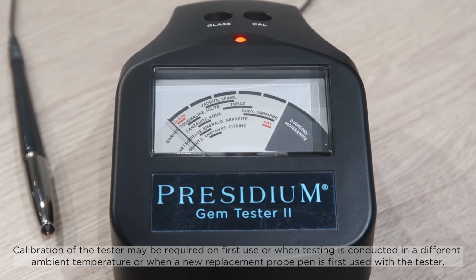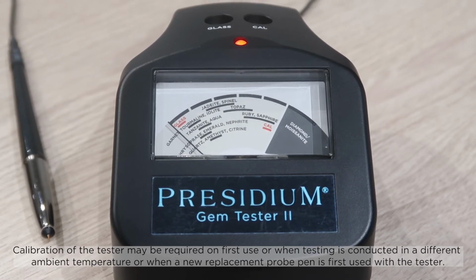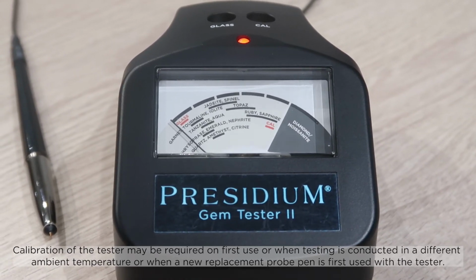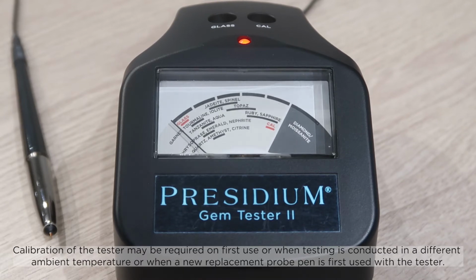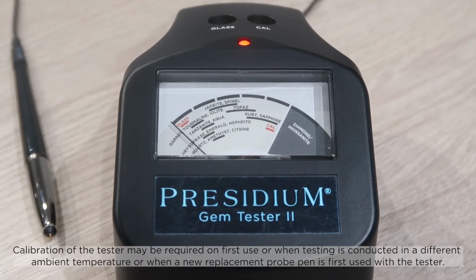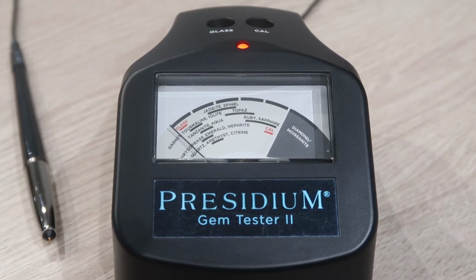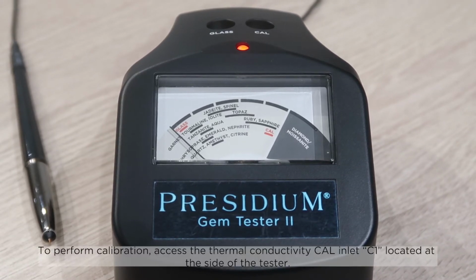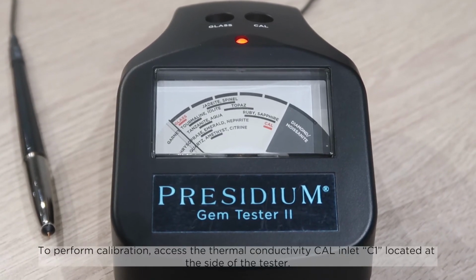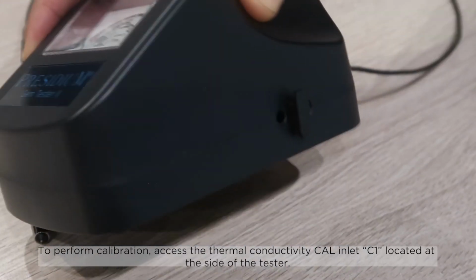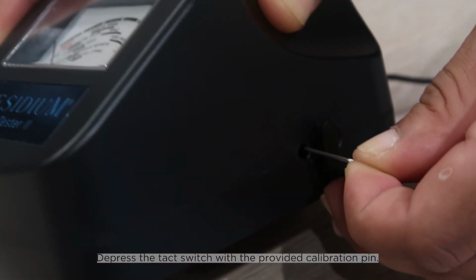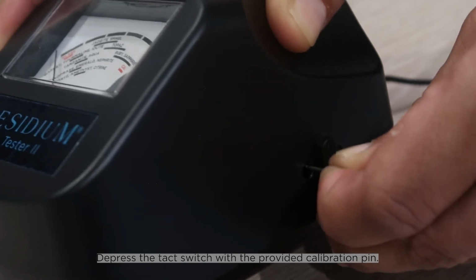Calibration of the tester may be required on first use, or when testing is conducted in a different ambient temperature, or when a new replacement probe pen is first used with the tester. To perform calibration, access the thermal conductivity cal inlet C1 located at the side of the tester. Depress the tact switch with the provided calibration pin.